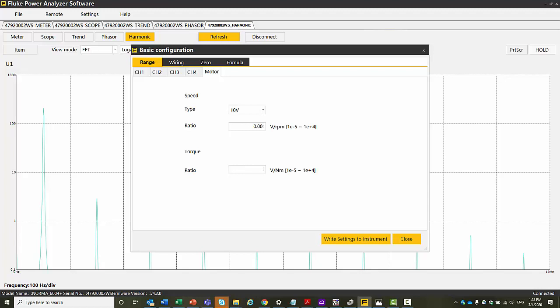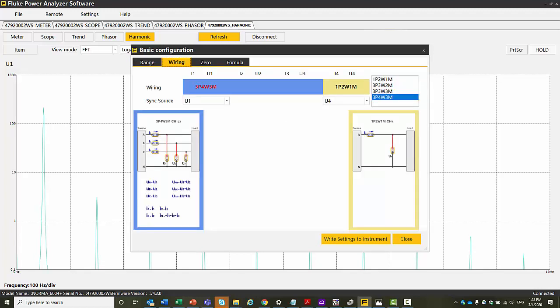Then we have the motor setup. So this is everything that you'll see on the instrument, and then the wiring diagram, that is how we're connected. In this case, we just have a single phase connection. You'll see these diagrams in the manual as well, and you can choose where you want to synchronize from, whether you want to synchronize from current or voltage or which channel. And if you have a split like this one where you've got 3-phase 4-wire and then you've got an independent channel on the end, you can choose 2 synchronization points. So if one of them is DC, for example, you can choose DC from here as well.